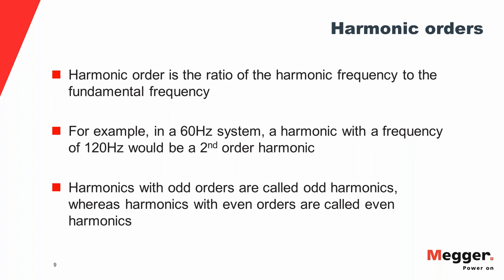The terms '20% third harmonic' and '20% fifth harmonic' refer to harmonic orders. Harmonic order is the ratio of the harmonic frequency to the fundamental frequency. A third harmonic means the frequency is three times the fundamental — 180 Hz in a 60 Hz system. A fifth harmonic is five times 60, which is 300 Hz. Harmonics with odd orders — third, fifth, seventh, ninth, eleventh — are called odd harmonics. Harmonics with even orders — second, fourth, sixth, eighth, tenth — are called even harmonics.